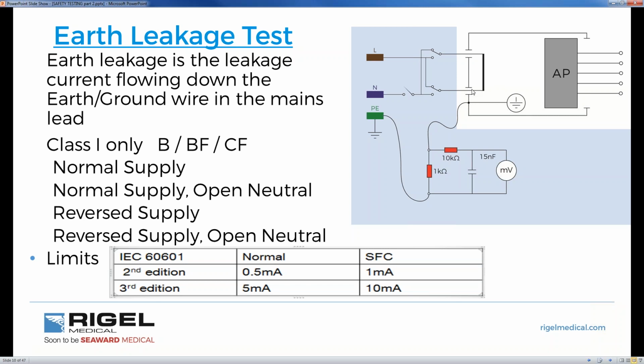So we have the current consumption to power the device. Well, inside the medical device there's lots of stray capacitance and lots of dielectric resistance, and somehow the current makes its way through all the stray capacitance back to the protective earth, and we measure it through our 1K body model back to the protective earth. So we have the live conductor coming in, all this stray capacitance, and then eventually it should find its way back to earth, and it gets measured internally within the safety analyzer, the Rigel. We measure voltage across this body model, and then that gets converted to current. And here are your pass-fail thresholds as far as current is concerned.